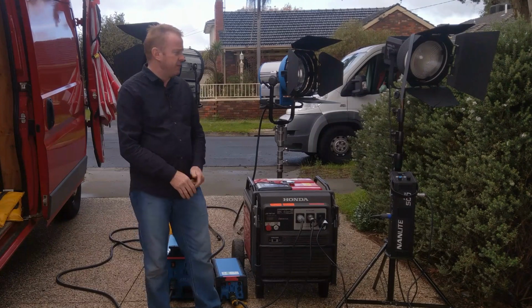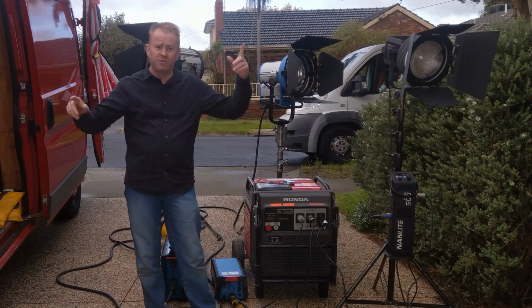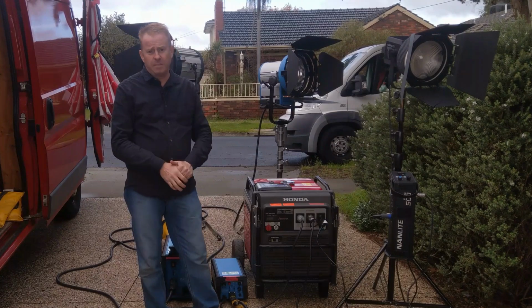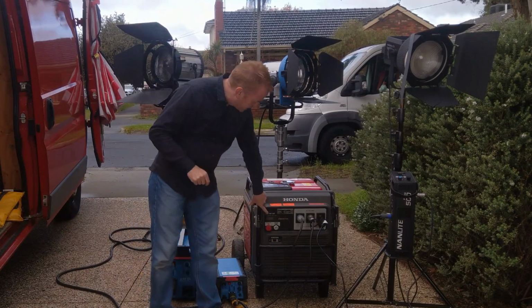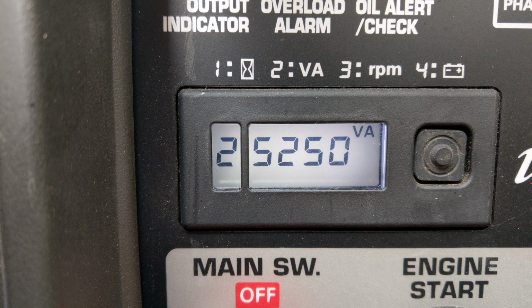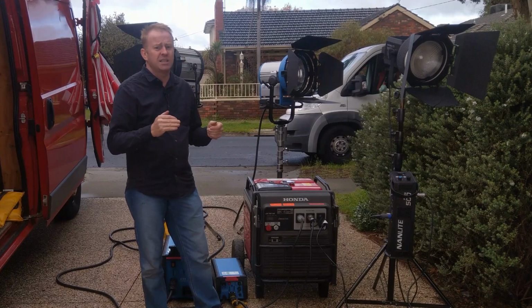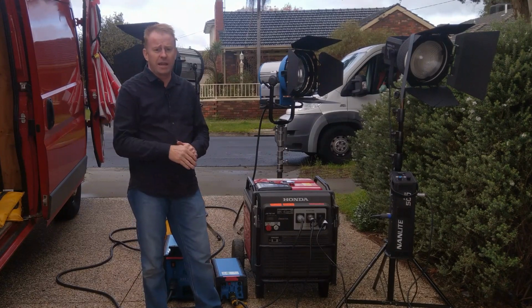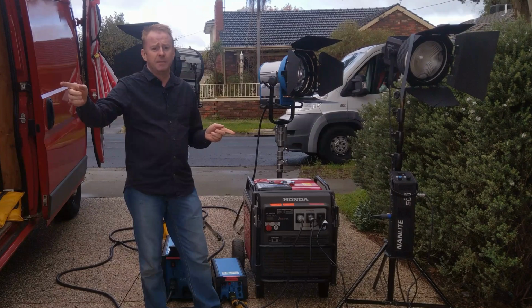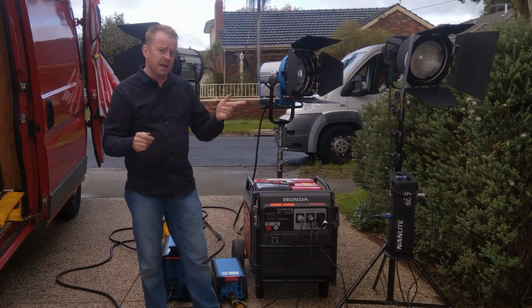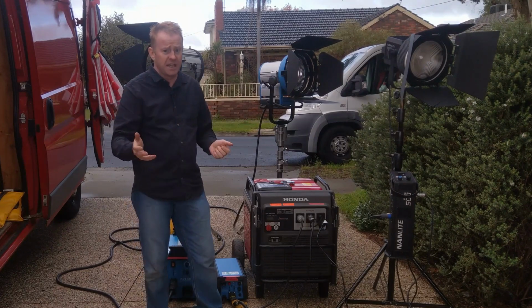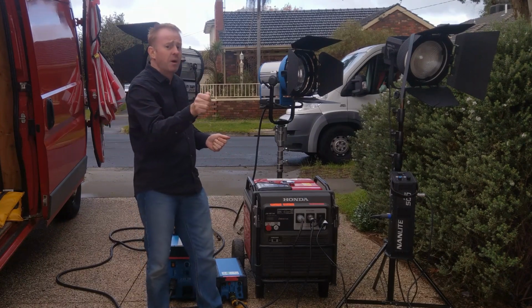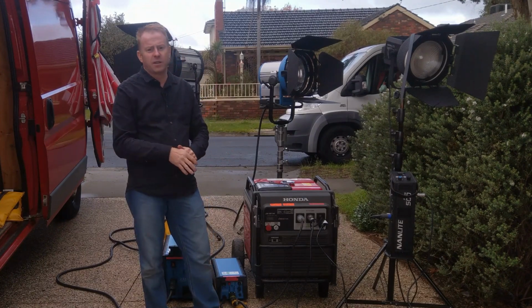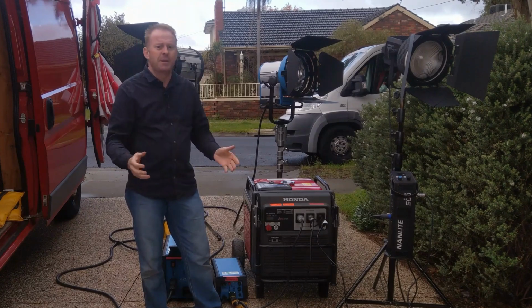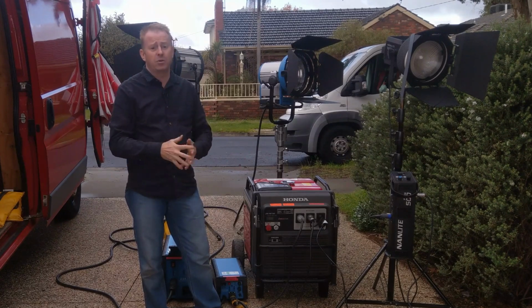Power cables. Okay, if I've got these 30 meters or 60 meters in different directions, you've got line loss over your power cables. So that's where monitoring comes in handy. A lot of these generators have monitors on them that tell you how much power is actually being pulled. So you can use that to check that you're still under your constant load ratings when you're running power extension lead. Now, quite often I'll have to go around a set after lunchtime or usually towards the end of the day and slightly dim my HMIs to keep everything under that constant load rating, because as the cables heat up, I get resistance and that increases the power draw.